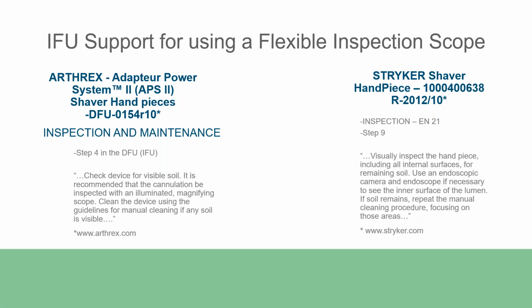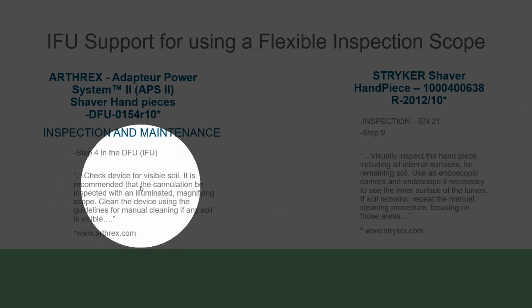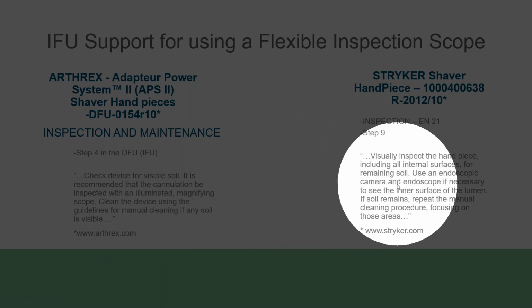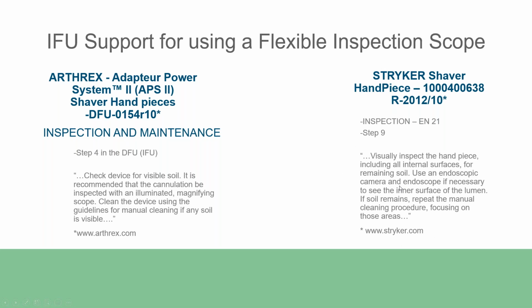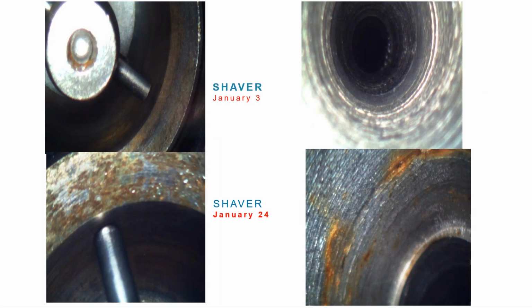So due to that issue, the manufacturer of the shavers went back and modified their IFU, and they included that they should actually look at recommending that cannulation come in here, look inside the cannulation, both visual inspection using the scope. Both the Stryker and Arthrex included that.